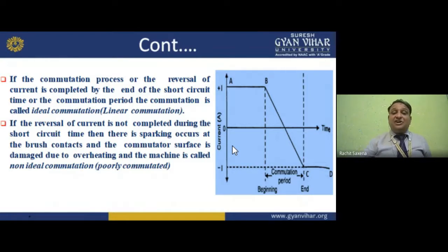Secondly, if the reversal of the current is not completed during the short circuit time, reversal means positive then negative, I am getting positive, then I am getting negative. If the reversal of the current is not completed during the short circuit time, then sparking occurs at the brush contacts, and the commutator surface is damaged.